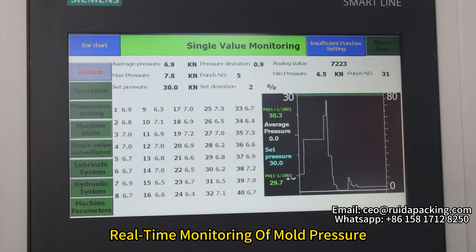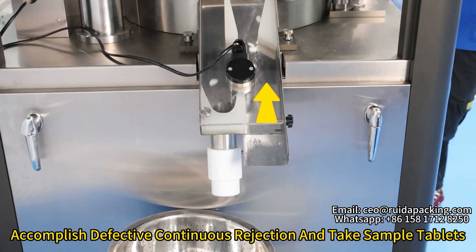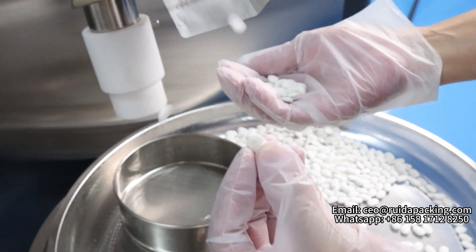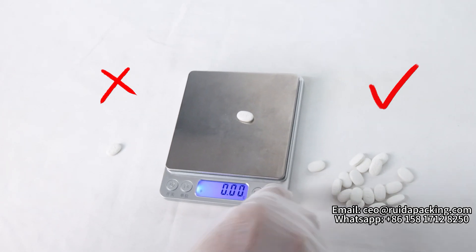Real-time monitoring of mold pressure allows continuous defective tablet detection, rejection, and sample tablet collection. Tablet weight error is less than 2%.